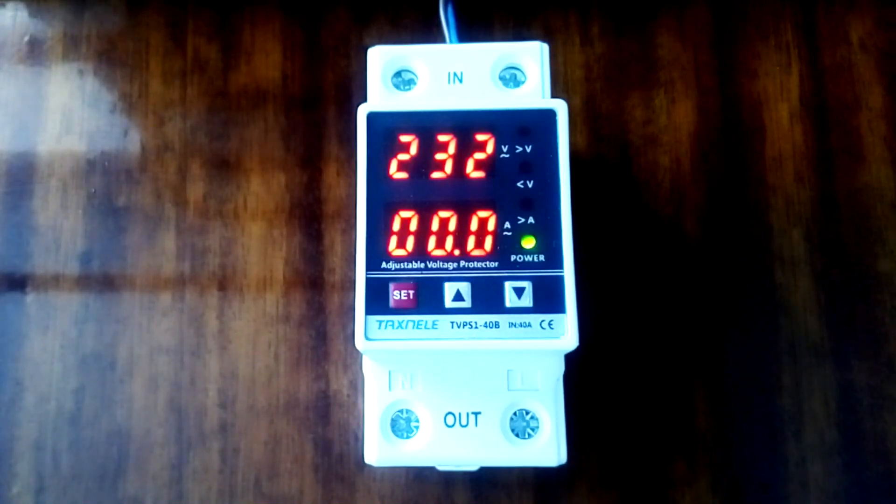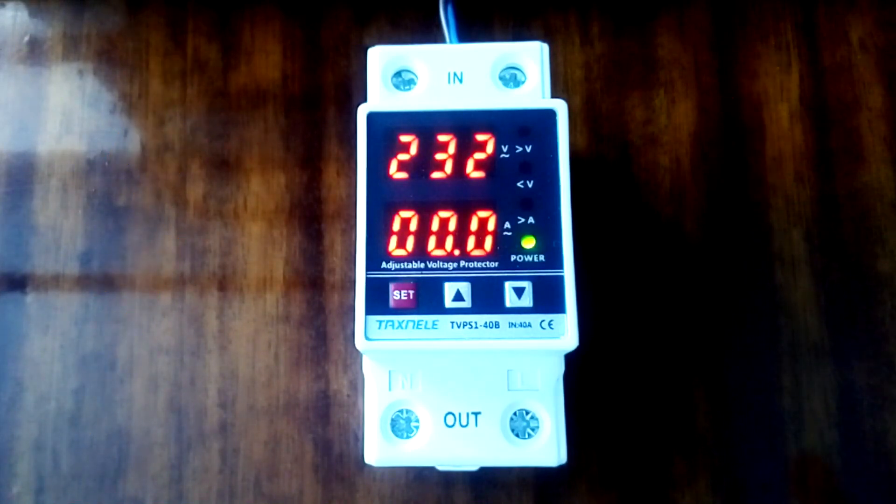But it is worth noting that this voltage relay will not protect against impulse noise resulting from a lightning strike. Here you need a faster response to shut down than a voltage relay can do. For this purpose, impulse noise protection devices are used. In short, they are called SPDs. I'm also going to make a video on them in the future.